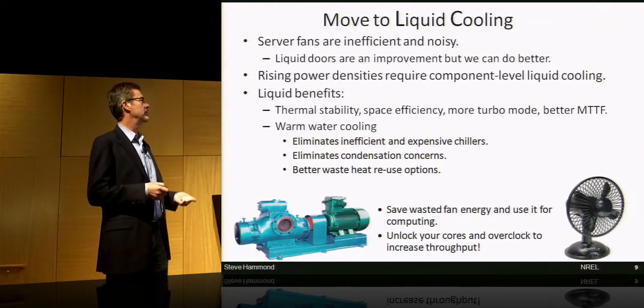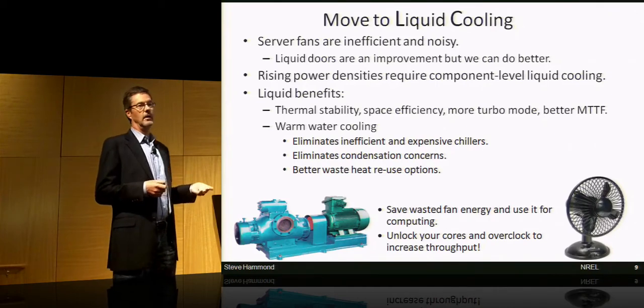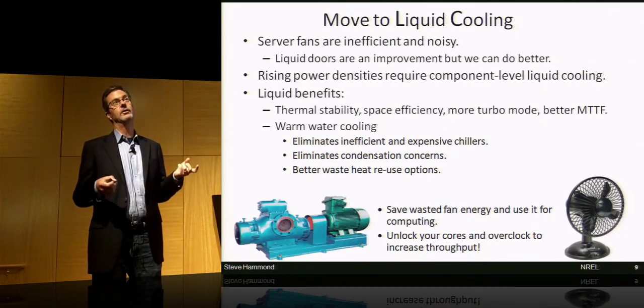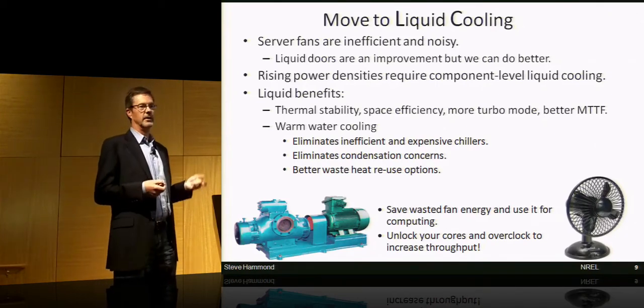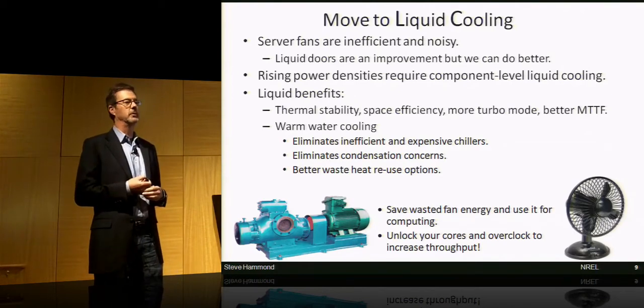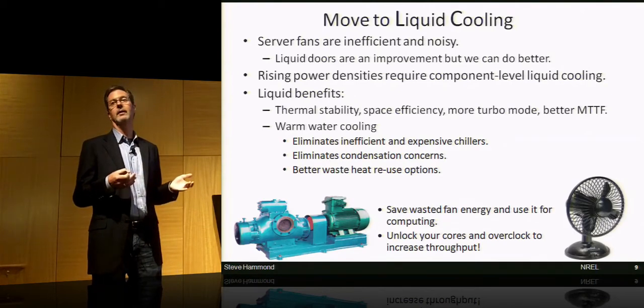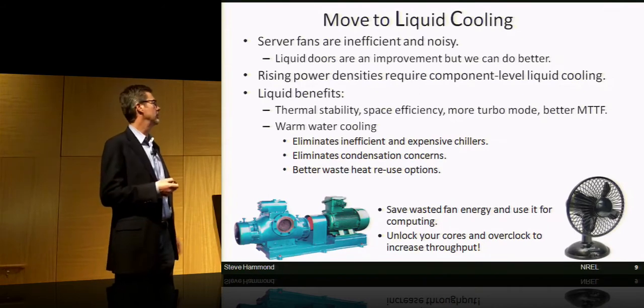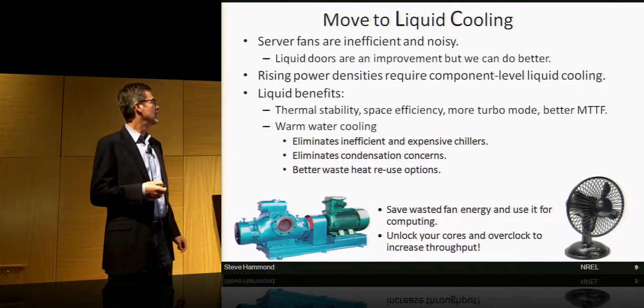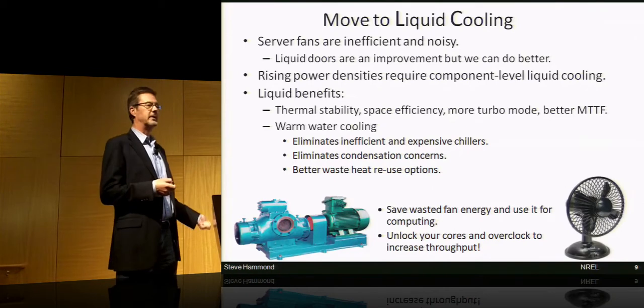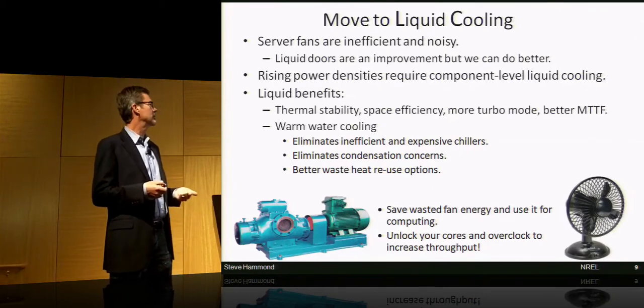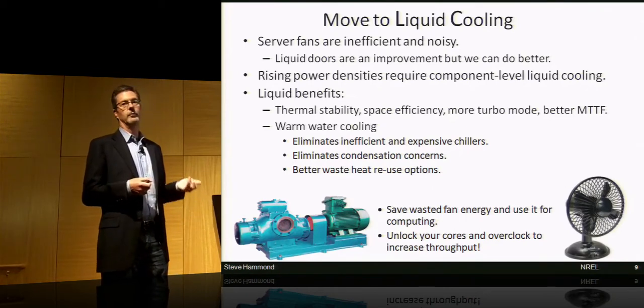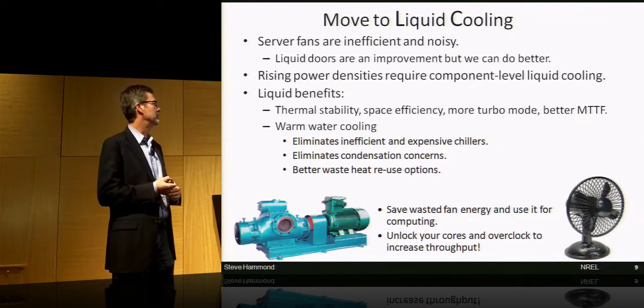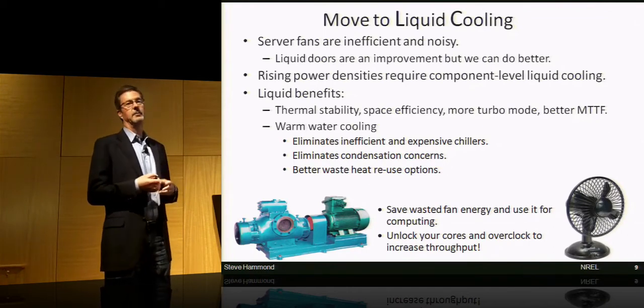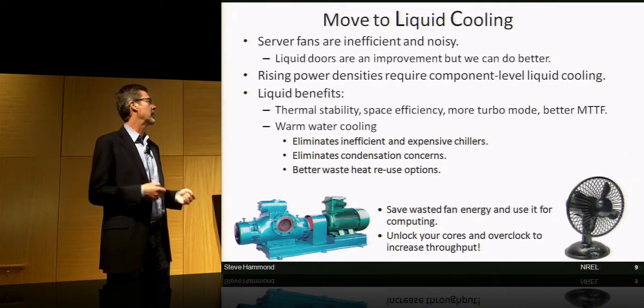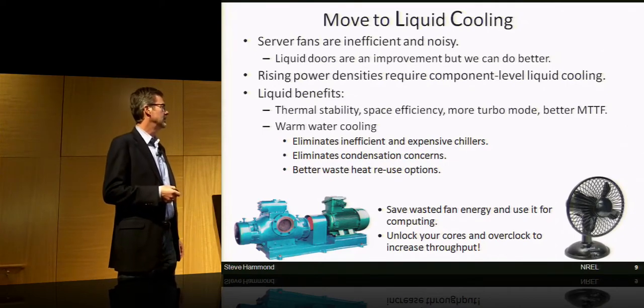Some of the benefits we've seen are thermal stability. The chips themselves, even though we're supplying warmer water, are kept cooler. We find we have much more opportunity to use turbo mode on our Xeons. You can eliminate expensive chillers if you start with warm water liquid cooling. You also eliminate condensation concerns. And by starting with warm water and getting hot water back, you have opportunities for waste heat recovery.